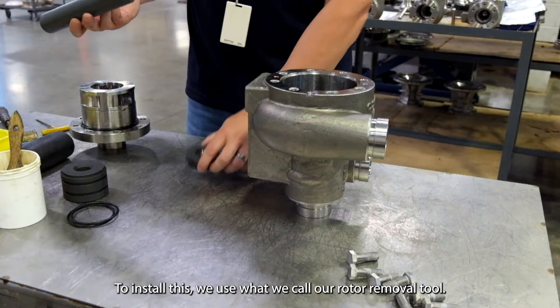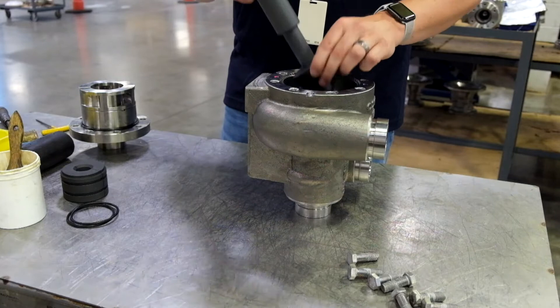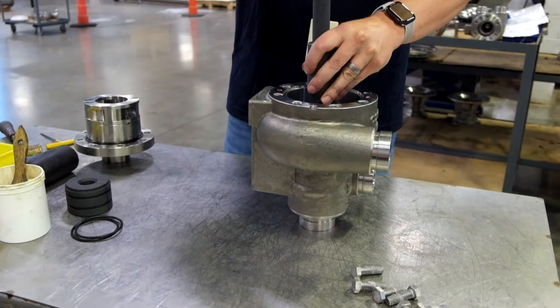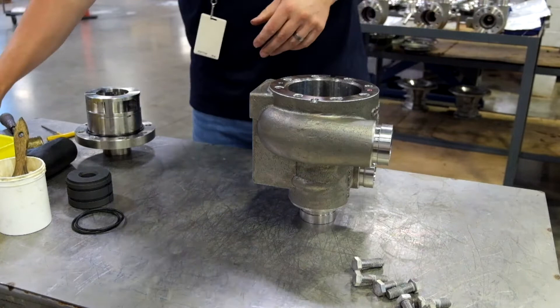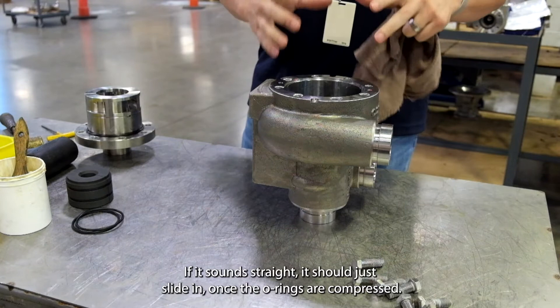To install this, we use what we call our rotor removal tool so that we can push down on the bearing without having to force any sharp edges on the wear surface for the rotor. You'll want to exercise caution when installing that because it is graphite and can chip if you force it in too hard or on too much of an angle. So if it's in straight, it should just slide in once the O-rings are compressed.